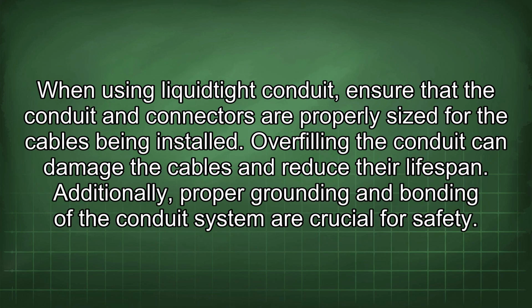When using liquid-tight conduit, ensure that the conduit and connectors are properly sized for the cables being installed. Overfilling the conduit can damage the cables and reduce their lifespan. Additionally, proper grounding and bonding of the conduit system are crucial for safety.